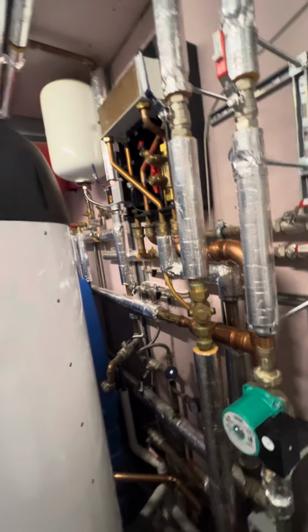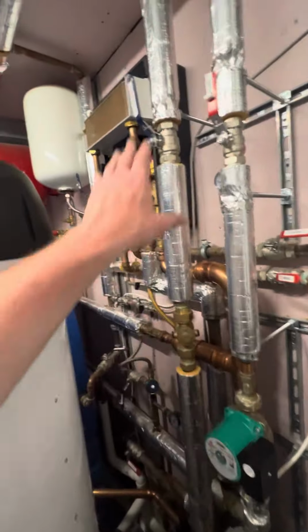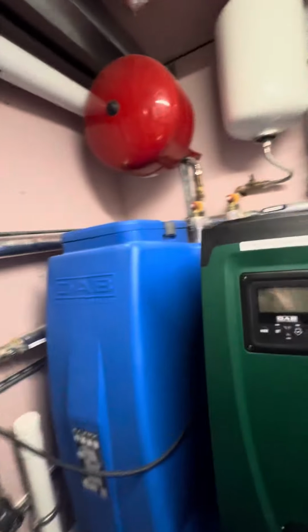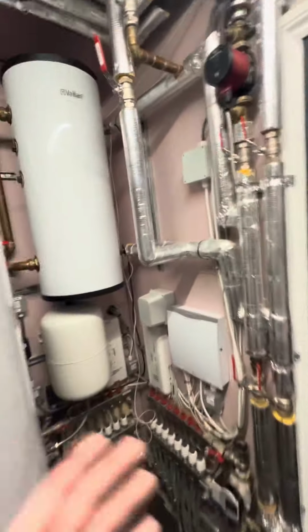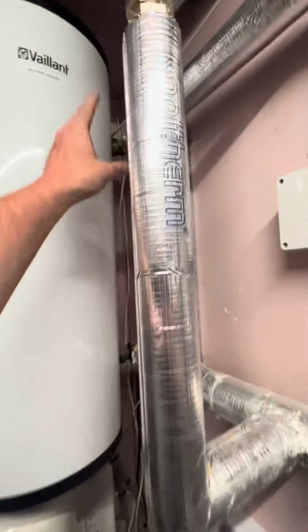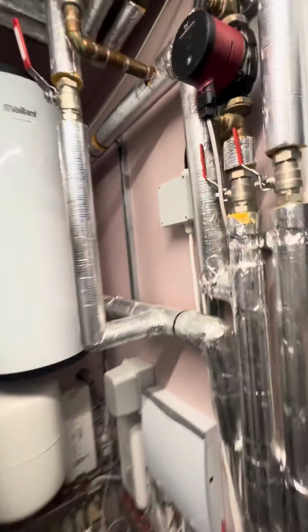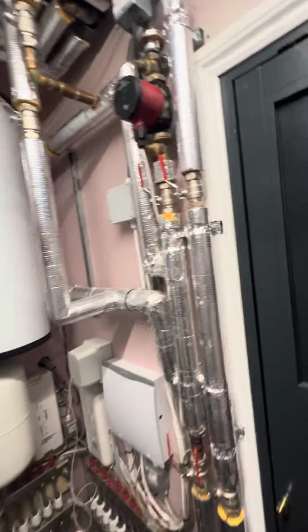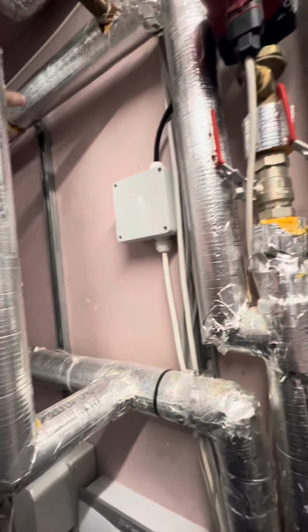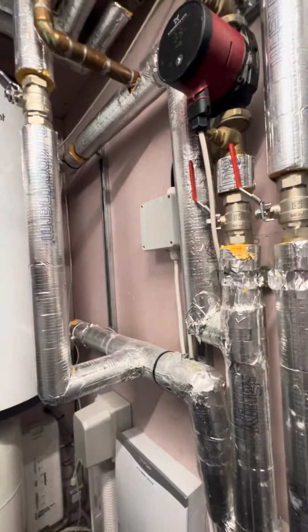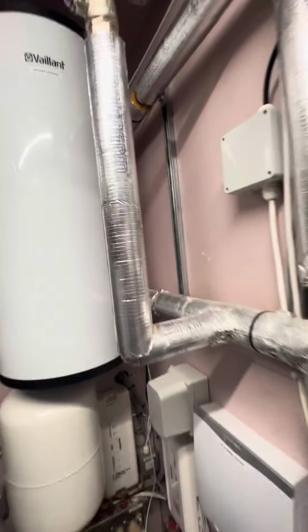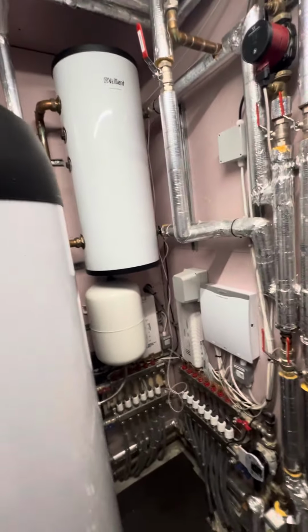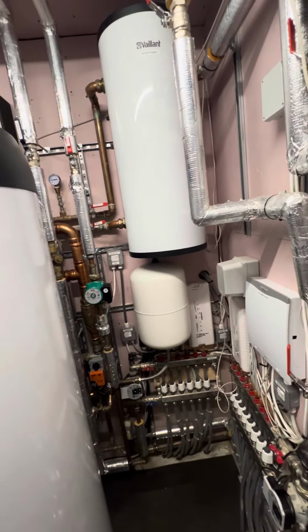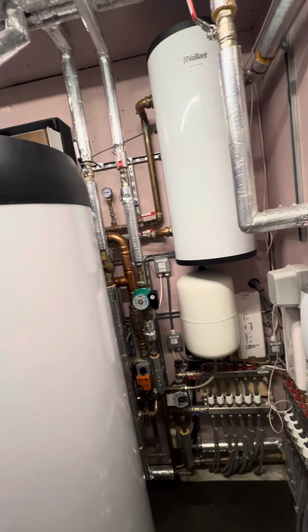And the first thing I'll do here is drain off the glycol, get rid of this system separation, then either pump straight through from the Vaillant built-in circulation pumps, or possibly if we did need to have the hydraulic separation, we would possibly just have one pump here to pump through the house, or we could just have the pumps for each manifold all around here. I wouldn't have them dotted around the house as they are, with more pumps upstairs as well. This is just not good for maintenance and not good for efficiency. So yes, not as efficient as it could be.